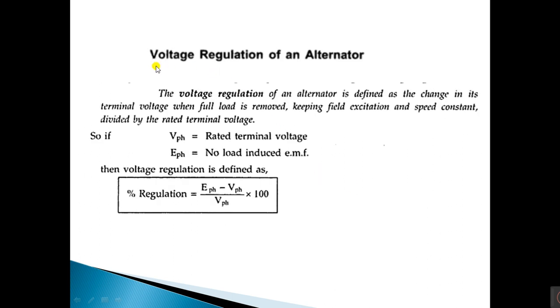Now, the voltage regulation of an alternator is defined as the change in its terminal voltage when full load is removed, keeping field excitation and speed constant, divided by the rated terminal voltage. Here V_phase is the rated terminal voltage and E_phase is the no-load induced EMF. The percentage regulation = (E_phase − V_phase) / V_phase × 100.